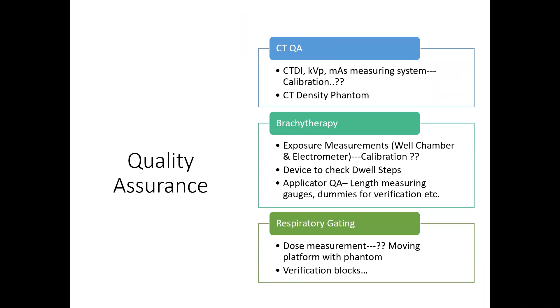If we have a respiratory gating system, we need to measure dose, which requires a moving platform in the phantom and the verification blocks. So we should consider that if we are going to buy linear accelerators with certain modalities, we must have all this associated QA with us. Putting a machine into clinical use without all this QA QC is not worth it. It's not suggested actually.